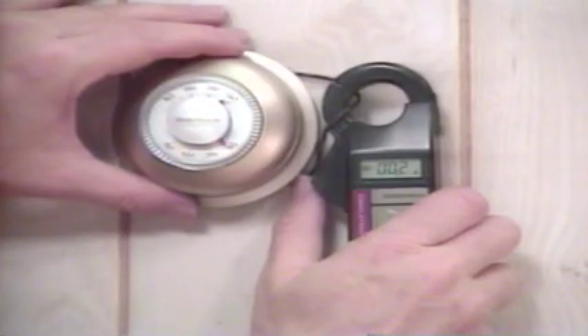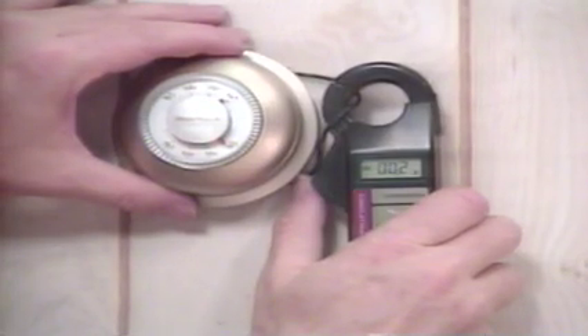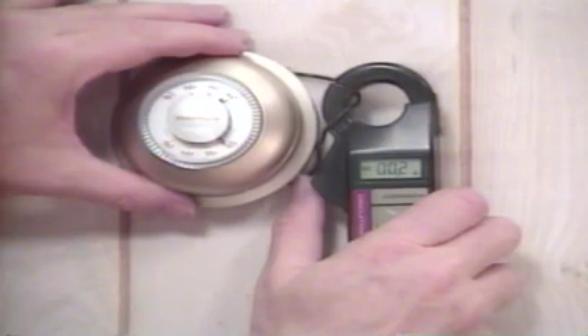If your ammeter has a selectable scale, always select the scale in advance of taking the reading, starting with the higher scale and moving down to avoid damage to the meter. You could use an ammeter to measure the current draw in the thermostat circuit in order to set the heat anticipator on a thermostat. You can measure the current draw anywhere in the thermostat circuit from the primary electrical source to the thermostat.